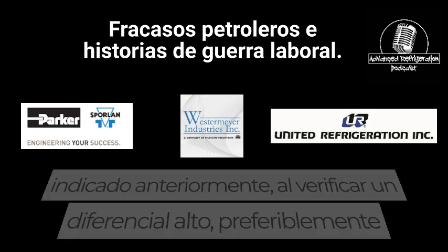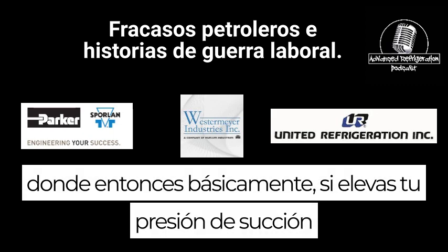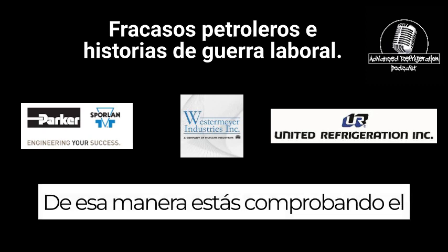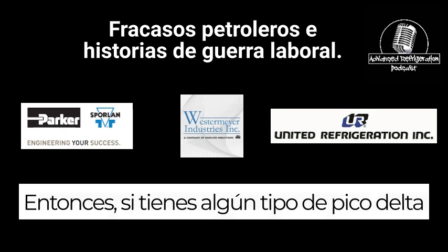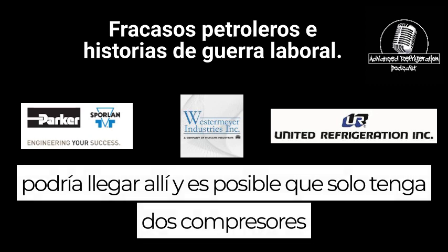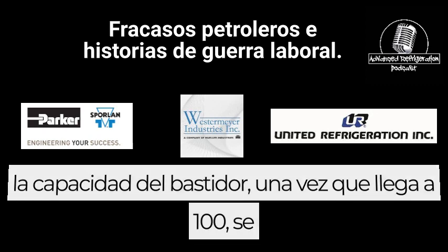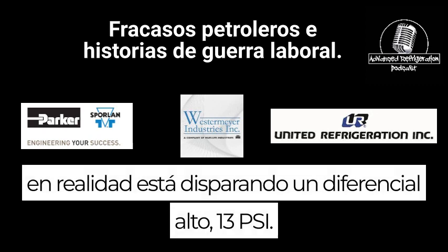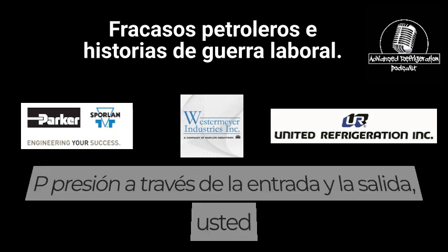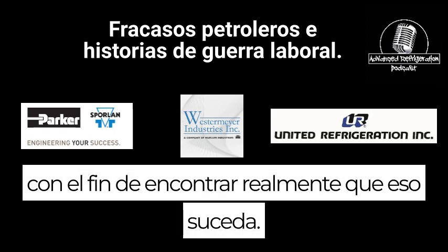Other than what Brett was stating before, when checking for a high differential, preferably just shut down the rack for a little bit. If you elevate your suction pressure high enough, technically all your compressors should come on. That way you're checking the full capacity of that rack. If you have a delta P gauge that is intermittently going off and on, you might get there and only have 2 compressors running. The delta P gauge isn't going on, but then you find out by graphing that once the rack hits 100% capacity, it is actually shooting a high differential of 13 PSI. So sometimes in order to find that high delta P across the inlet and outlet of the coalescing filter, you might need to run all the compressors.